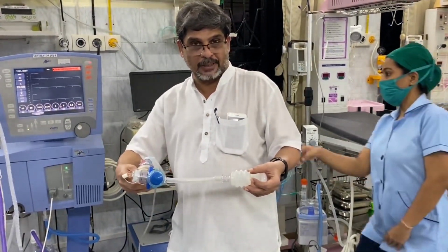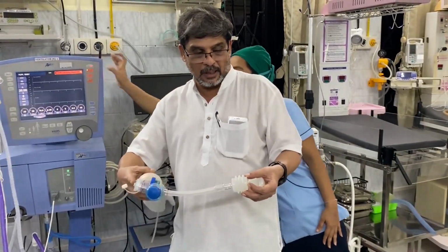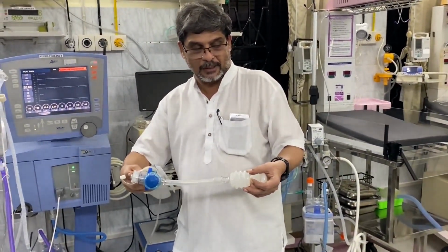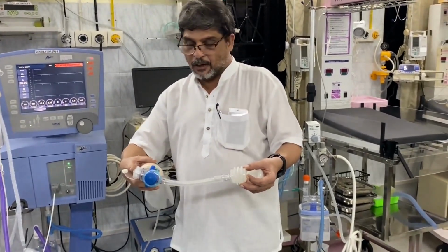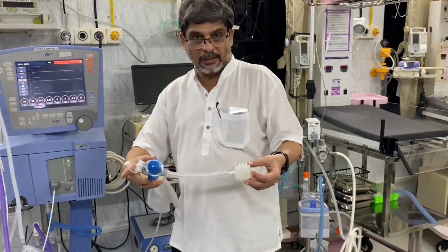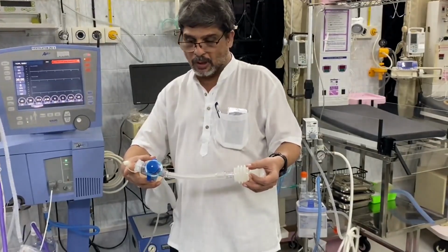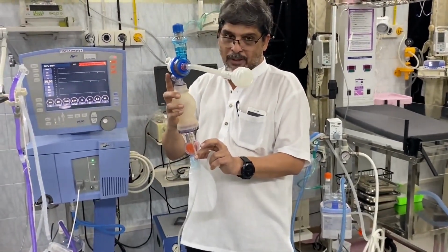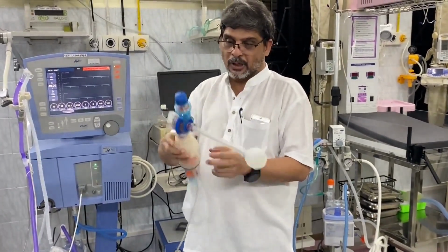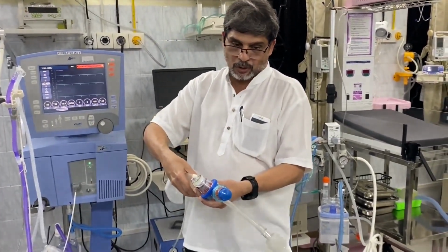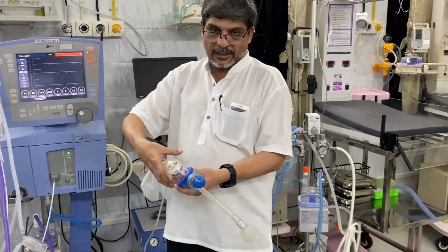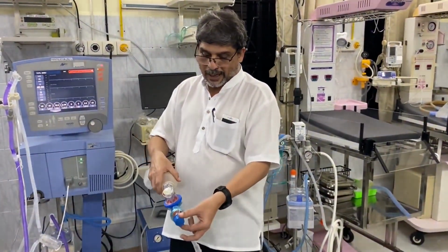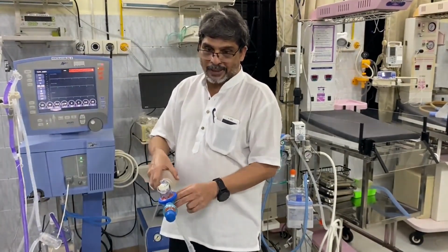Peak inspiratory pressure, PEEP. If you allow it to go back totally, the positive end-expiratory pressure is 0. You decide the FiO2 on this, how much oxygen you want to give to the baby through this oxygen port. Then with peak inspiratory pressure, you give the breath.